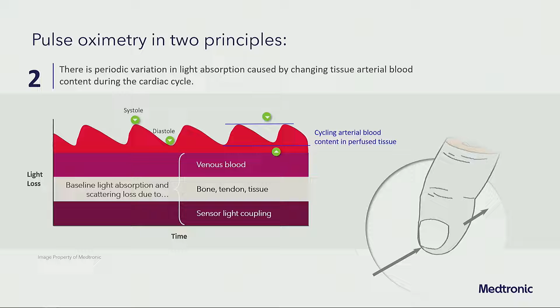So the way that the pulse oximeter derives the SAT is using a calibration curve. And so at high saturations, remember that oxyhemoglobin absorbs higher in the near infrared. So at high saturations, you're going to see a different profile of your signal amplitude, or the ratio of red to infrared, than you will for low saturation. And all of that is related to a calibration curve. So you get this R number that's red modulation over infrared modulation, and you can relate that to the SAT. So it's a calibration curve, it's built into the technology, but this is how it's coming up with a number. It's measuring the changes in pulsation, and it's relating that to a previously derived calibration curve.